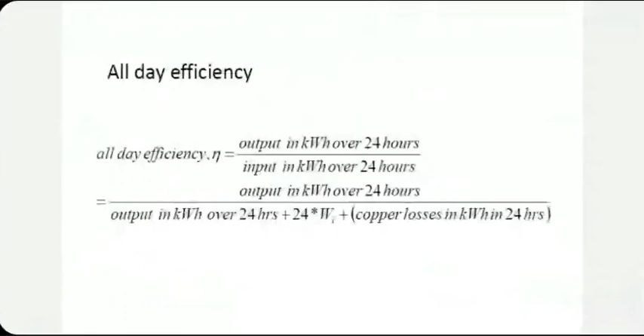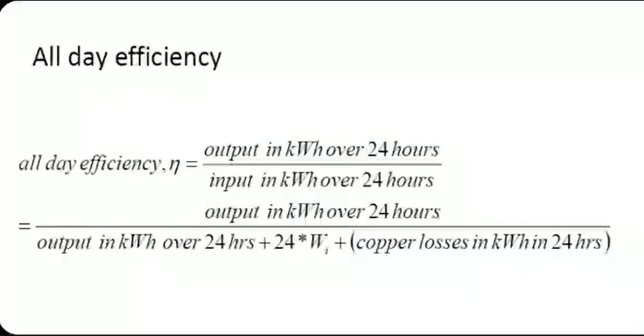The load of the transformer changes all the time, so it's probably a better idea to measure total energy output over a 24-hour period versus total energy input over the same period, and compare the two by taking the ratio to figure out all-day efficiency, which is energy output divided by energy input over a given period of time, normally 24 hours, all day.